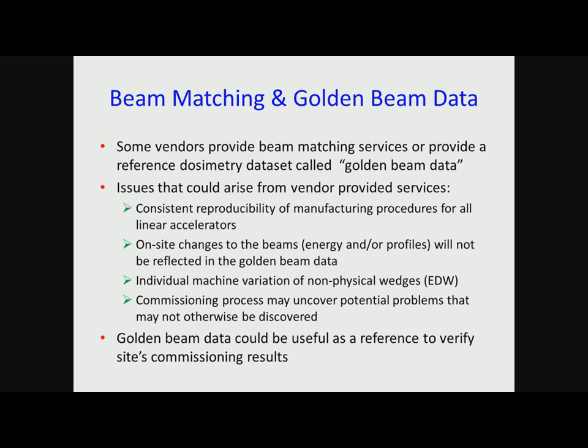There are a lot of mechanical parts that go into these Linacs, and they're slightly different from each other. They're close, but not identical. When the Linac engineer comes on site, they make on-site changes to the beam. They're changing depth dose and the bending magnet voltage, making sure your profiles are just what you like. This may not be the same as the golden beam data. It might be slightly different.